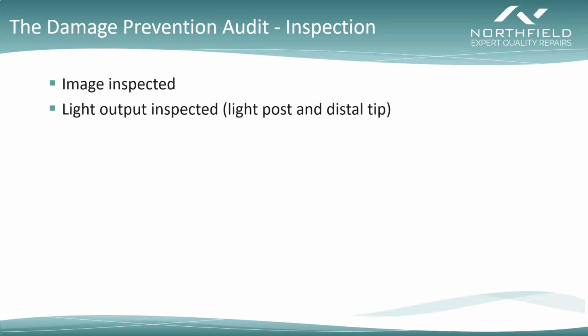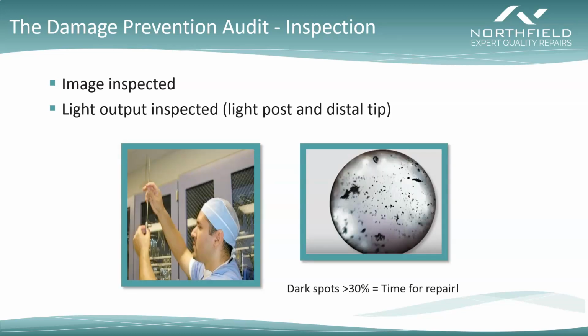Now, after the scopes move out of decontam and into the prep and pack side, we want to put a lot of emphasis on the inspection process. This is critical for making sure that those devices that are faulty do not make it into a surgeon's hand and therefore affect that procedure. So we want to inspect the image, we want to inspect the light output. Inspecting the light output is very easy.